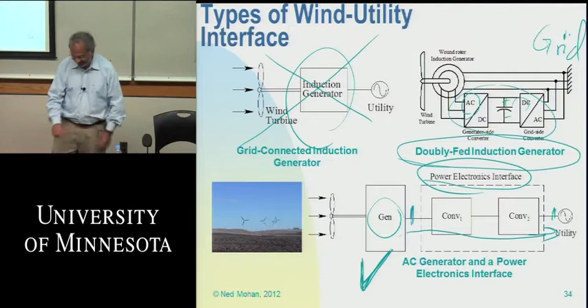And when you have such large power levels, 5 to 10 megawatts, gears become the biggest reliability issue. So to eliminate gears, you have so-called direct drive—your turbine may be running at 10 RPM, and so is the generator. Imagine your generator running at 10 RPM, very low speed. In that scenario, there's not much option but to use permanent magnets. So very large wind turbines use permanent magnet offshore. And as you know, the cost of permanent magnets is skyrocketing, so there's a big dilemma.